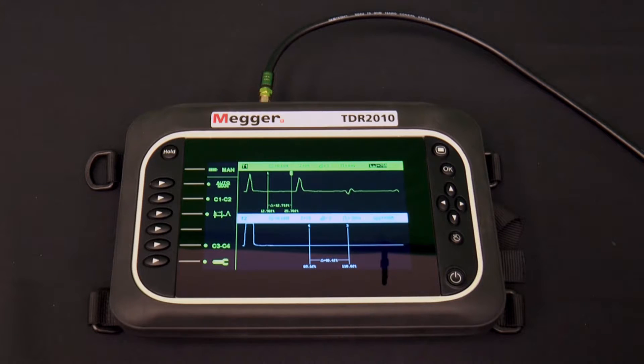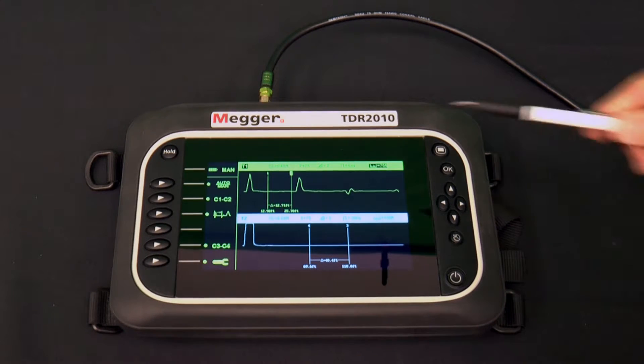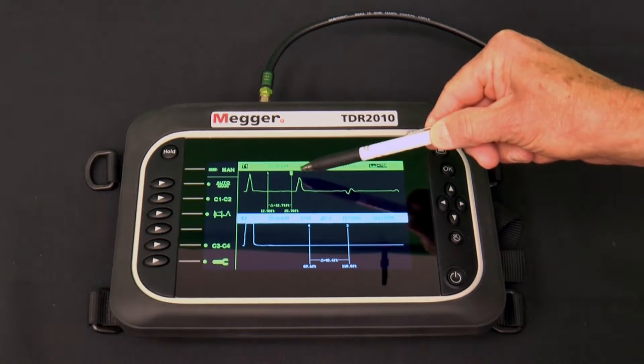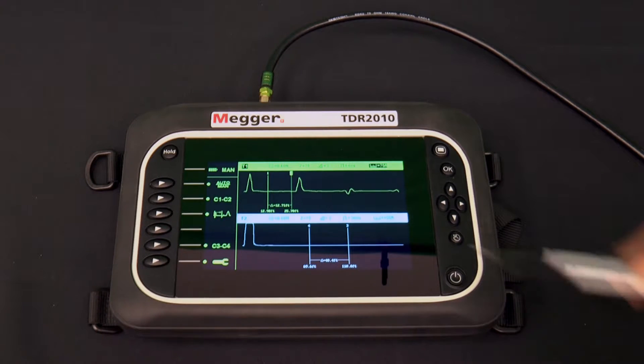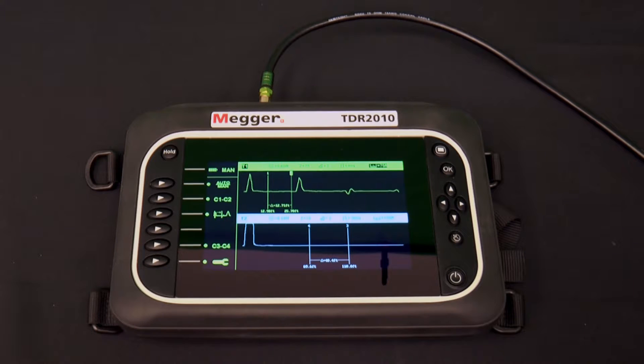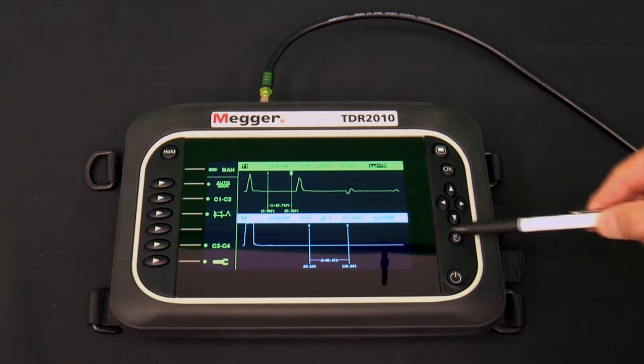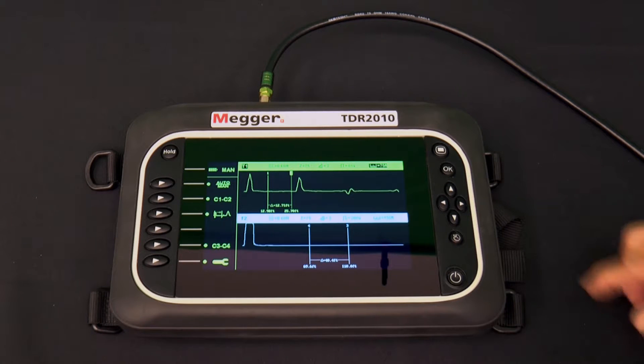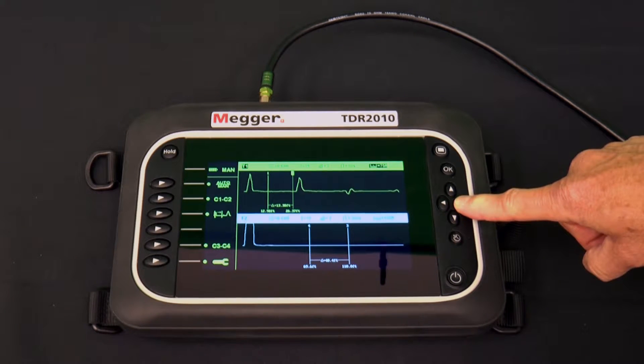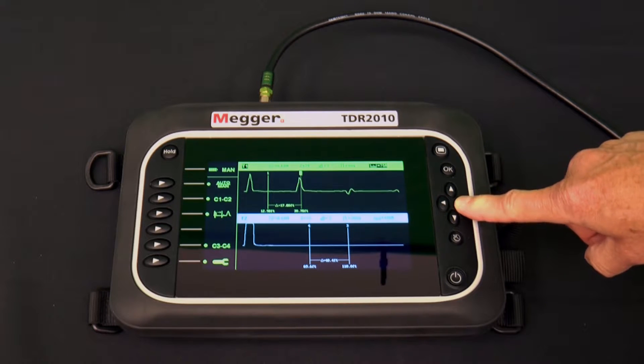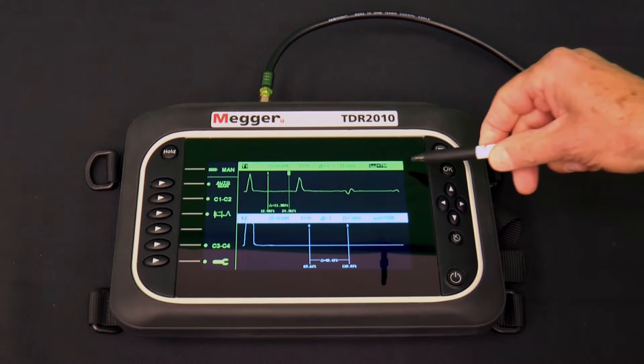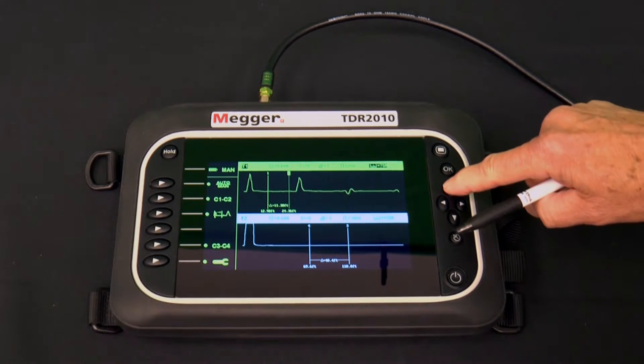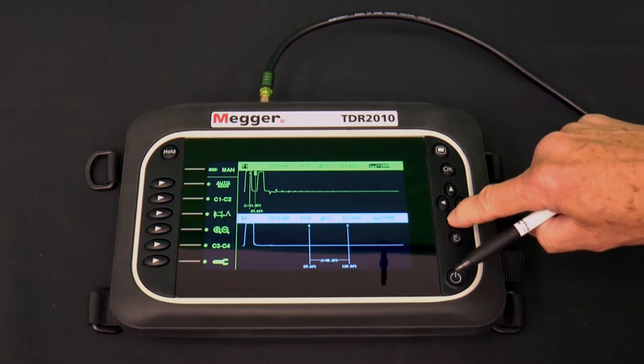In this case, there are four cursors on the screen. The active one — the one that is controlled by the left and right arrows of the navigation group — is a dashed line. The other three are solid lines. The left or right arrow of the navigation group may be bumped or held down to move the active cursor. If it is held down, the speed with which the cursor moves increases the longer it is held down. Using the up and down arrows of the navigation group, increase the amount of cable displayed on the screen for the active trace until an event is visible.